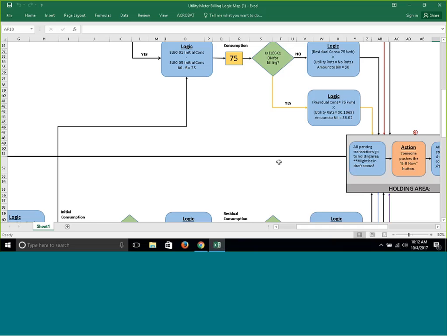And so then, we go and ask engineers, okay, engineers, what the hell's going on? Is the meter wrong? Did we blow out all the windows and have to reheat the building to make up for it, whatever, right? And so sometimes the answer is, nope, that just is what it is, and we leave the readings the way they are, and great. And sometimes the answer is, oh, look at that, there was something really weird going on with that meter, and so they give us a correction, and we go into the system, we go into Tririga, and we correct the reading or correct the consumption.